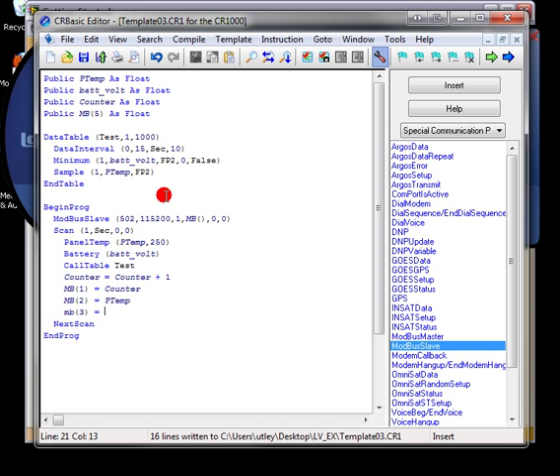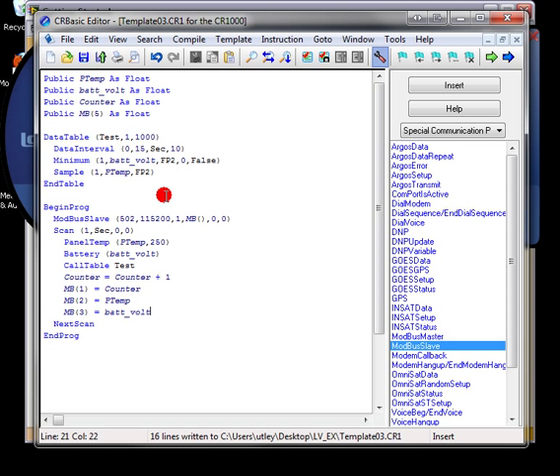And the third will be batvolt. Now though these variables are being put into consecutive positions in an array in CRBasic, they in fact require querying two registers by the Modbus master.